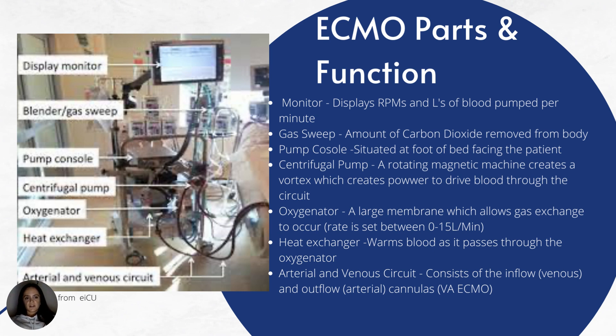The heat exchanger is a component of the machine that warms the blood as it passes through the oxygenator. Patients are often hypothermic just due to the circuit, so the heat exchanger is commonly used to keep the patient and their blood warm.